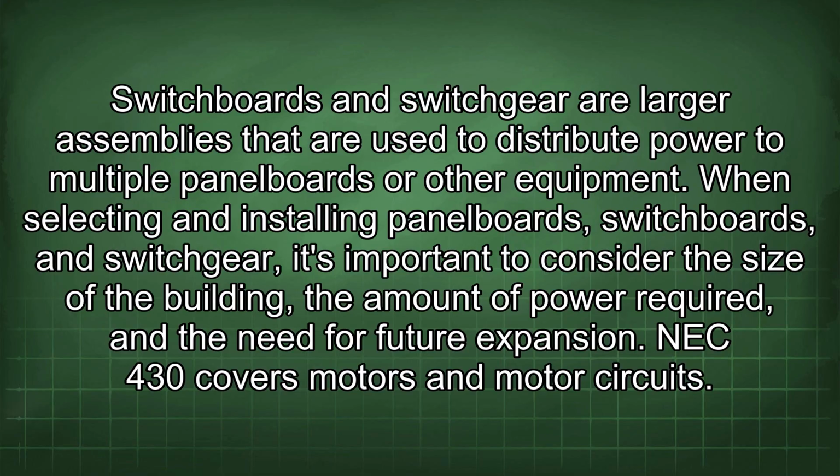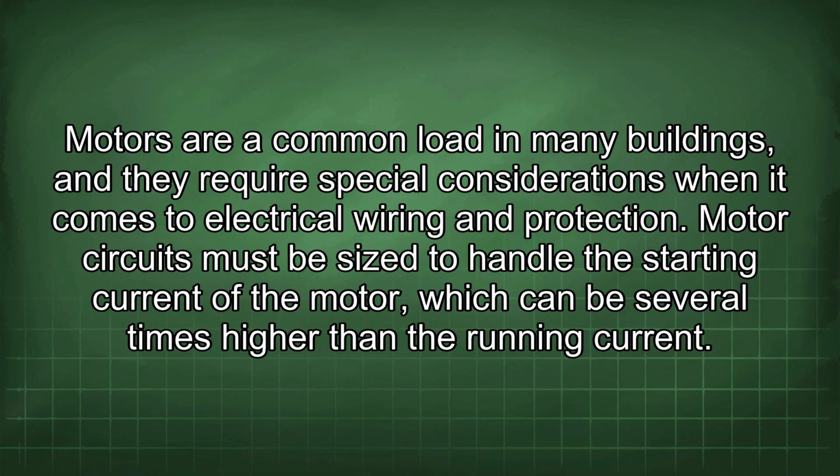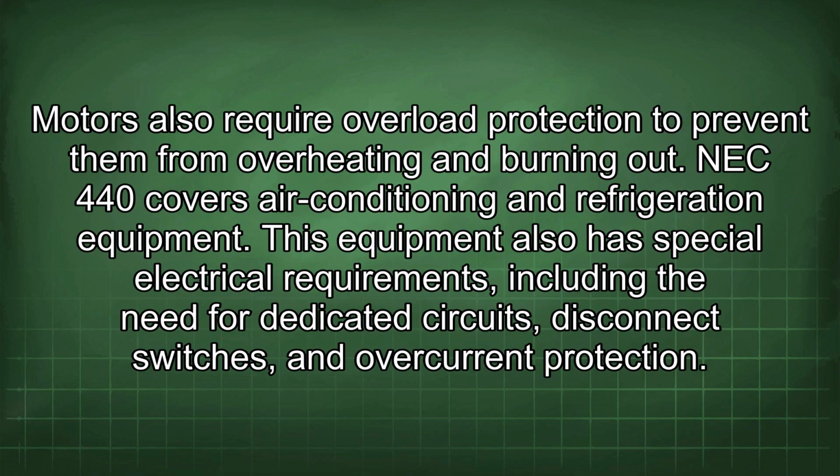NEC 430 covers motors and motor circuits. Motors are a common load in many buildings, and they require special considerations when it comes to electrical wiring and protection. Motor circuits must be sized to handle the starting current of the motor, which can be several times higher than the running current. Motors also require overload protection to prevent them from overheating and burning out.